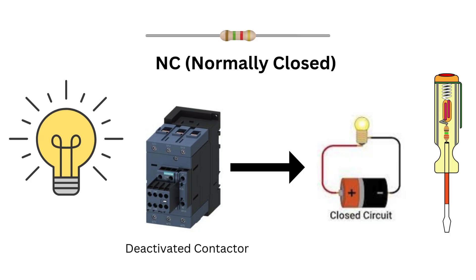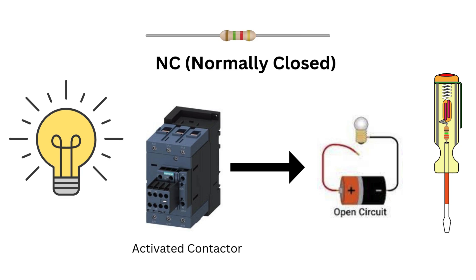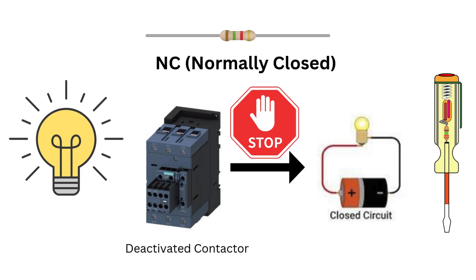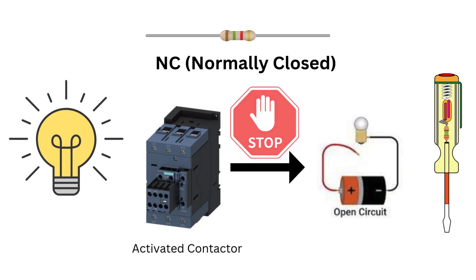Next up, we have NC, or normally closed contacts. Here the contacts are closed when the contactor is not powered, meaning the circuit is complete and electricity can flow. But when you power the contactor, it opens the contacts — click — and the electricity stops flowing. NC contacts are perfect for safety features. For example, in an emergency stop system, you might want the circuit to be live until you press the stop button. When you press the button, the contactor powers up and opens the NC contacts, cutting the power and stopping the system instantly.